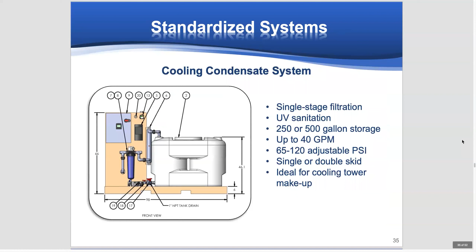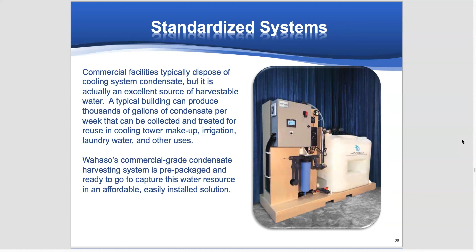This is a condensate system for air handling units. We created a package system because a number of people over time asked for them, so it became a standard product. You can typically collect 2 to 3 gallons per minute from an air handling unit, times 1,440 minutes a day, which can be a sizable volume of water. That condensate water is usually quite clean and can be sent up to the cooling towers, which is typically what we do with it.